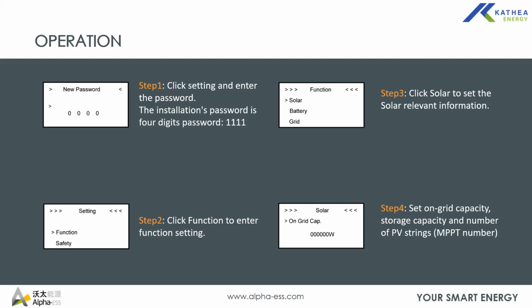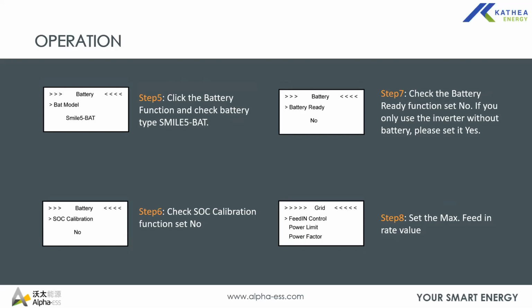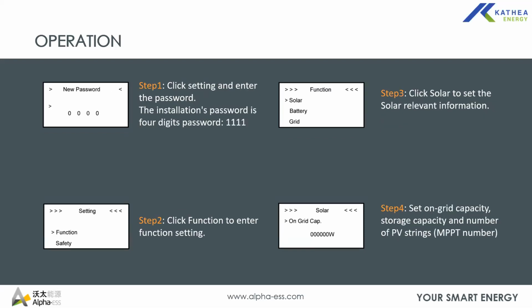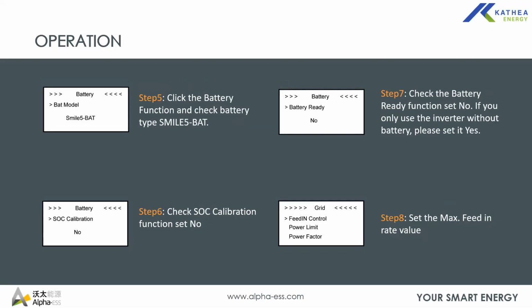So on solar, when you press enter, it will prompt you to input the amount of your PV array, to specify the PV array that you put on the roof for the MPPTs. The other setting on solar will automatically pick the number of strings connected, and you just have to scroll to confirm that it picked all the strings there. And then the next setting will be the battery.